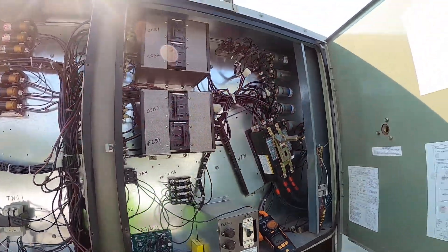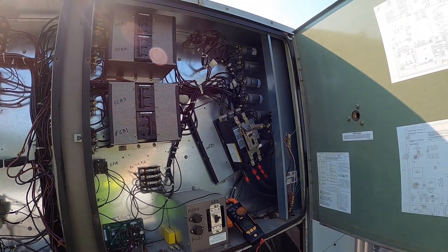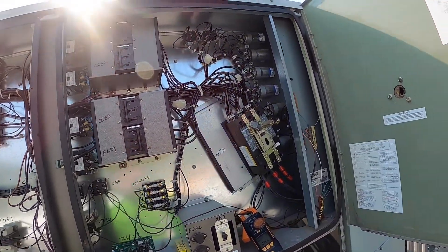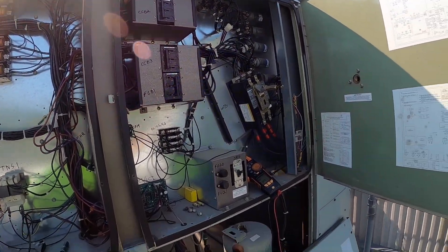So I'm just going to put some new fuses in there, get the three motors going, and make sure there's no other problems. Then I've got to try to locate a spare motor or a new motor and get it picked up for today. It's supposed to be another heat wave coming through — mid-90s today in New Jersey — so I definitely would like to get my customer back online and move on to the next one.